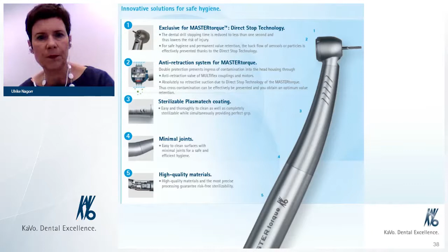We have very, very minimal joints in the instruments, and we have for all instruments, turbines and low-speed instruments or motor-driven instruments, selection of homogeneous material. The KaVo tradition is here to use stainless steel as a material, not only for the sleeves but also for the inner drive parts, which provide longevity of the instruments after many cycles of thermodisinfection and sterilization all over the working time.